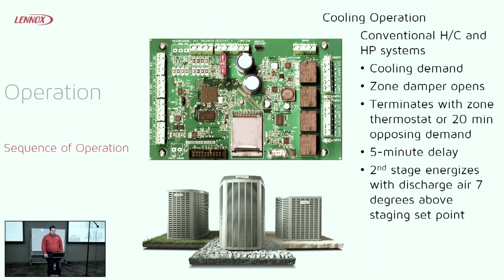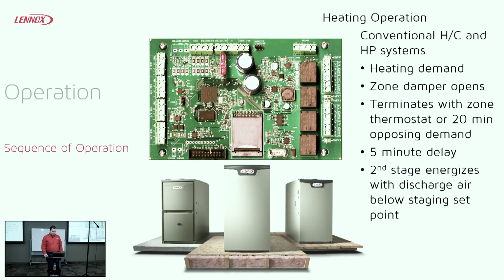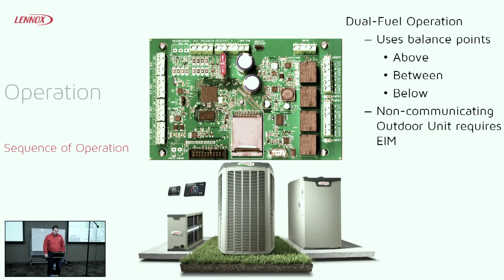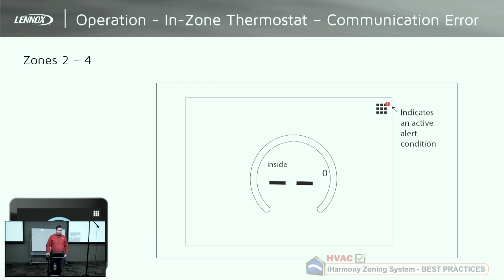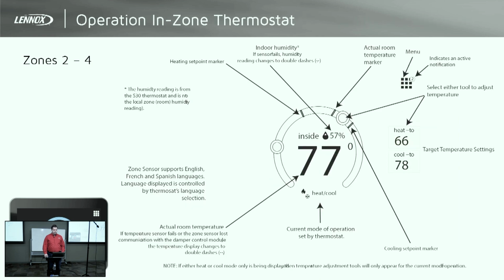A lot of this is things we've already discussed, but probably the only other issue to be aware of, if you're doing a dual fuel setup where you've got a communicating furnace and a non-communicating heat pump, we're going to require an EIM module for communication for that to be able to function. Something else that's good to know, if you're getting dashes on the zone control or on the zone stat, that's going to be an indication of communication problems. So just something to be aware of. Again, that's where you look at your comm signal.